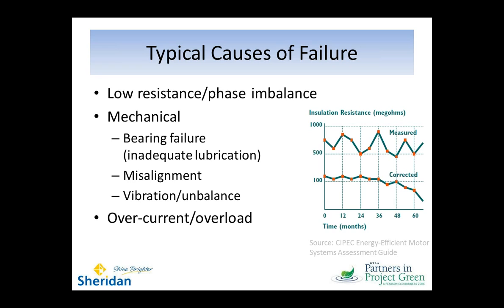And also, just by consciously going out and looking for where a motor seems misaligned, maybe occasionally measuring voltage to see if the phases remain in balance, and doing this test shown on the right, which is a test of the insulation of the motor to verify the integrity of the insulation, essentially by putting a high voltage on the windings and comparing the voltage you've put on the winding against the frame voltage, you can measure how much resistance is still in that.